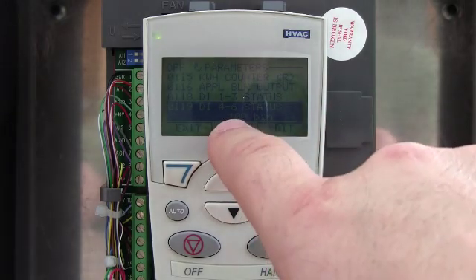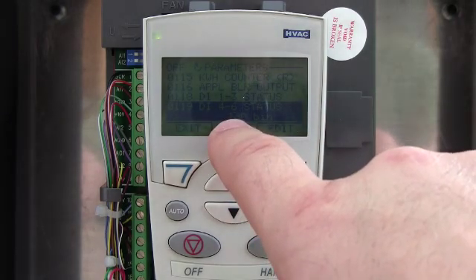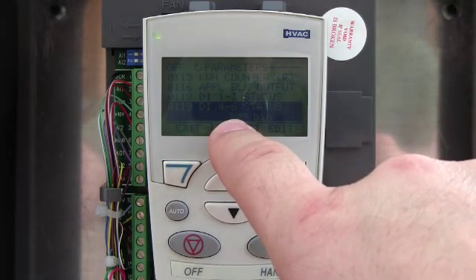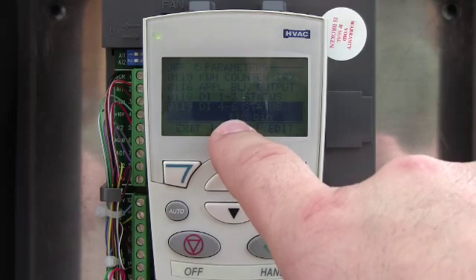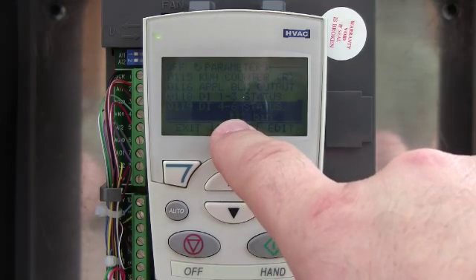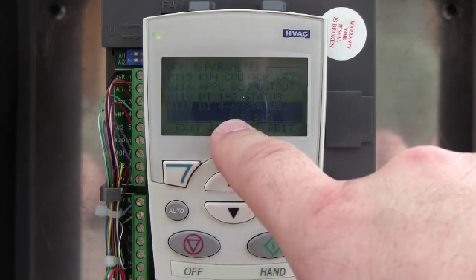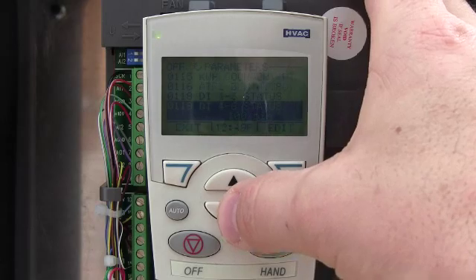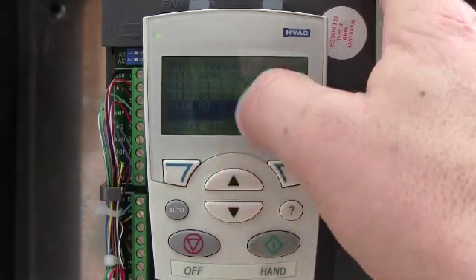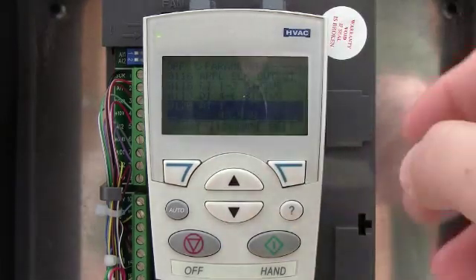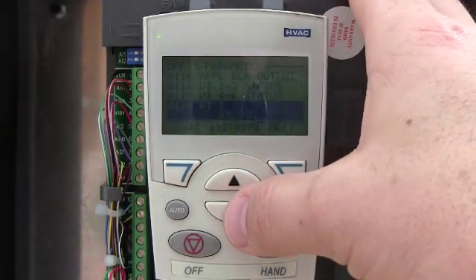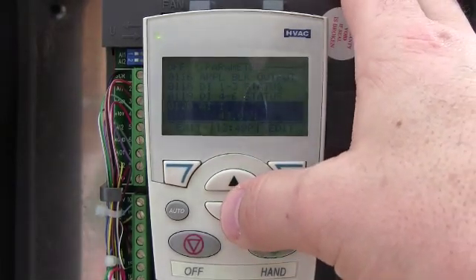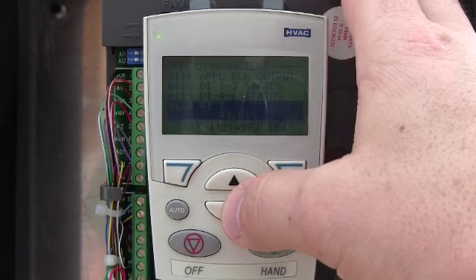Digital input four is my run enabled, so I'll leave that one closed, otherwise the drive will go into alarm. Five and six — I'll leave four on. So that's kind of nice — that's a way of proving without a meter whether the drive sees that start-stop signal or safety circuit.